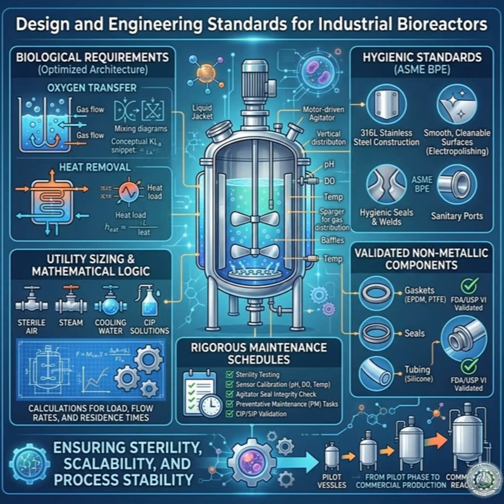Because if you quietly switch the brand of an O-ring, that new rubber might have a slightly different chemical curing agent, which could leach into the batch and alter the biological product. So tracking the exact provenance of every consumable is a regulatory mandate. This plays directly into the total cost of ownership, which the source tackles head-on. It gives a very specific context for North American deployments. It states that if a reactor cannot be serviced by local technicians, or if the spare parts cannot be obtained rapidly, the total cost of ownership skyrockets, rendering any upfront savings from a cheap purchase price totally irrelevant.